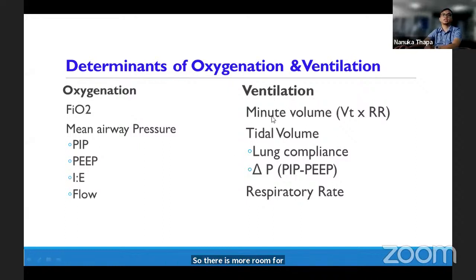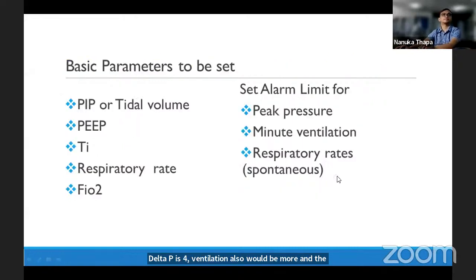In ventilation, the minute volume is tidal volume times respiratory rate, in liters per minute. Tidal volume depends on the lung compliance also. In a case where there are stiff ribs, the lung compliance will be less. If the patient got a muscle relaxant, the lung compliance will be more. And delta P, like I said before, is the peak inspiratory pressure minus the PEEP. If the delta P is more, the ventilation also will be more. And the respiratory rate also determines the ventilation.